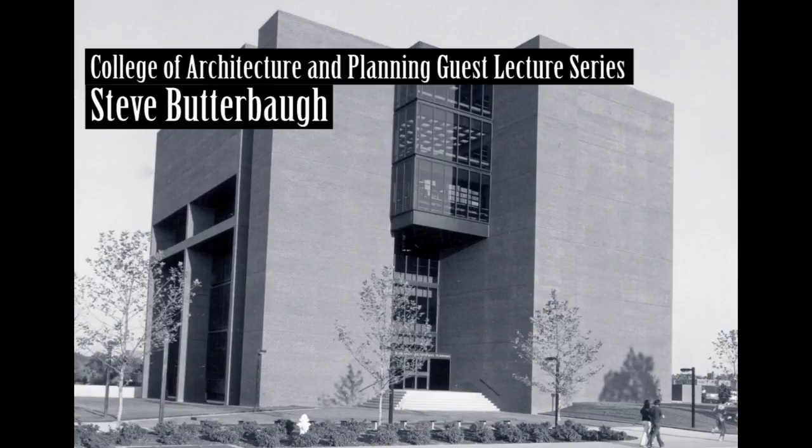For the hospital, the proposals were the following: 1, replacement windows with thermal pane and thermal break frame. 2, buying a small air handler to serve the 24-hour emergency room in order that the main air handler, which served the large clinic area next to it, could be shut off except for the 9 or 10 hours that the building was occupied.